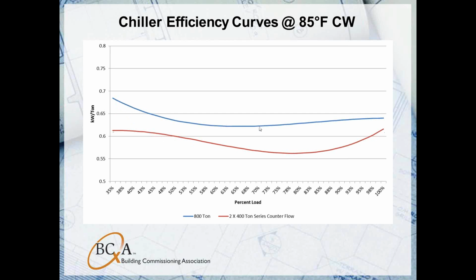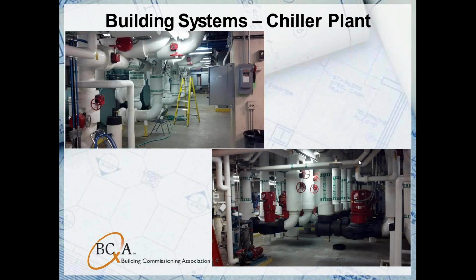It's also good to note that operated individually, chillers 3 and 5, which are the series counterflow chillers, have an efficiency curve that's similar to the 800-ton chillers. So here's just some actual pictures of the plant itself. On the upper left, you can see the chillers all in a row, and a little bit out of the frame on the left is the plate and frame heat exchanger. And in the bottom right, you can see the condenser water pumps on the left and the chilled water pumps on the right.